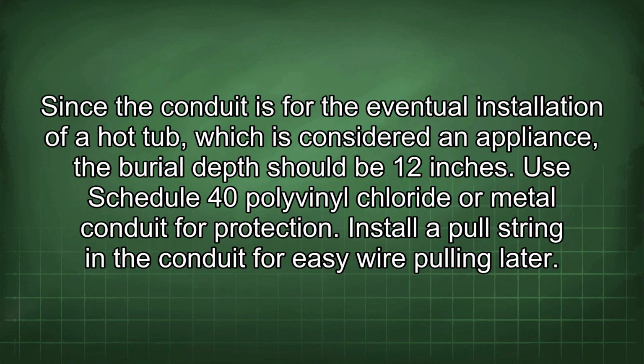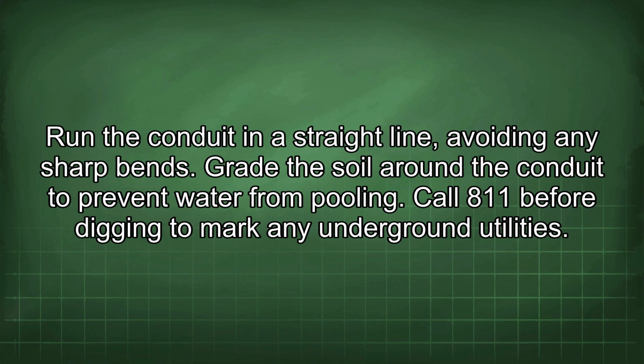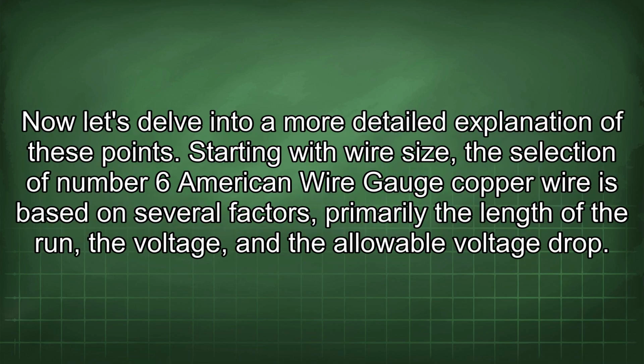Since the conduit is for the eventual installation of a hot tub, which is considered an appliance, the burial depth should be 12 inches. Use Schedule 40 polyvinyl chloride or metal conduit for protection. Install a pull string in the conduit for easy wire pulling later. Run the conduit in a straight line, avoiding any sharp bends. Grade the soil around the conduit to prevent water from pooling. Call 811 before digging to mark any underground utilities. Now let's delve into a more detailed explanation of these points.